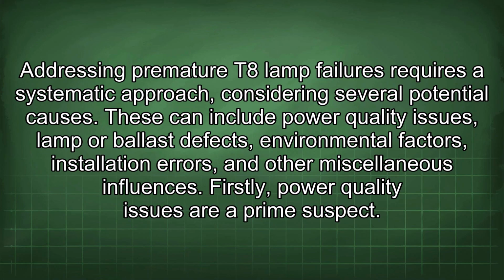Addressing premature lamp failures requires a systematic approach, considering several potential causes. These can include power quality issues, lamp or ballast defects, environmental factors, installation errors, and other miscellaneous influences. Firstly, power quality issues are a prime suspect.